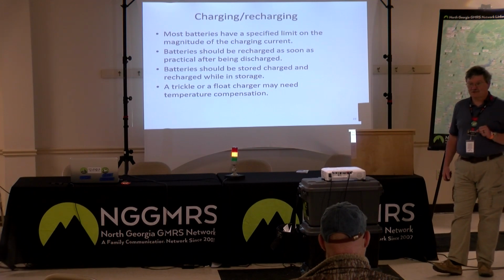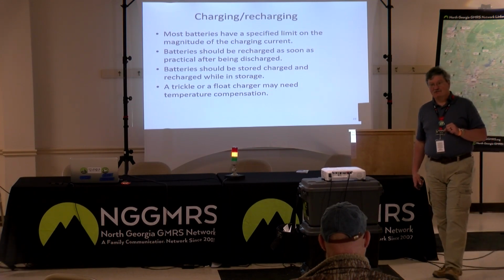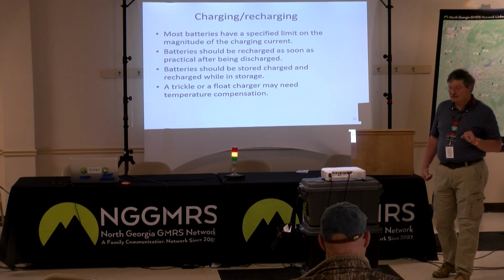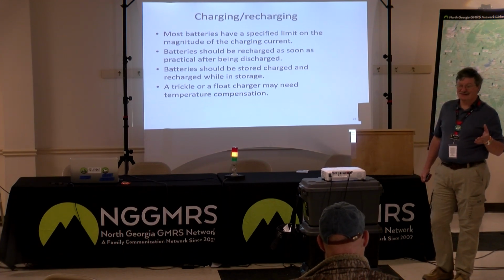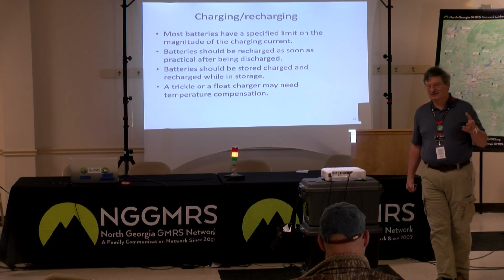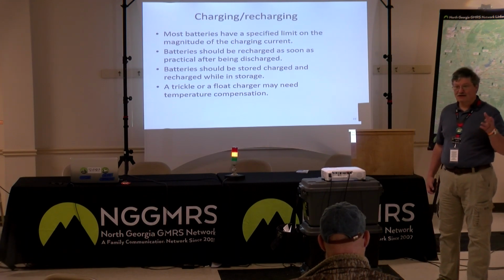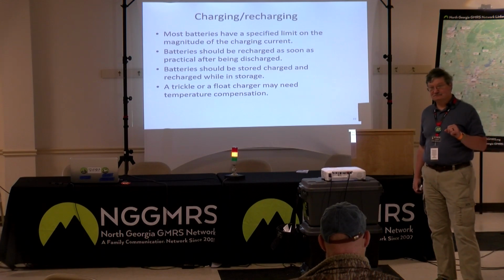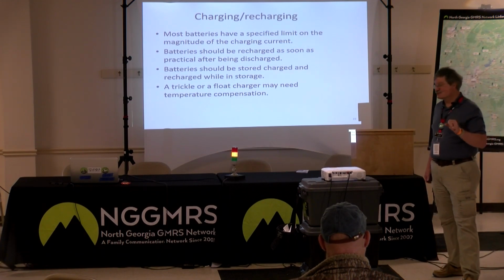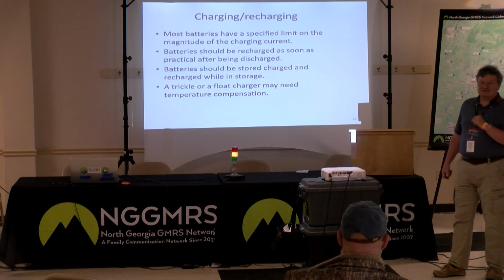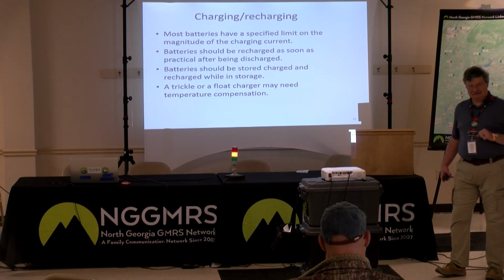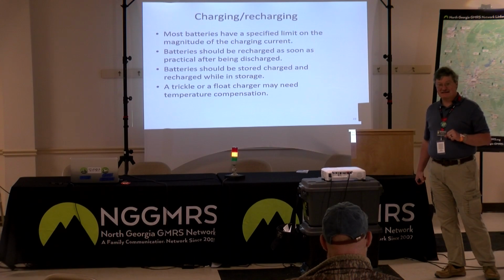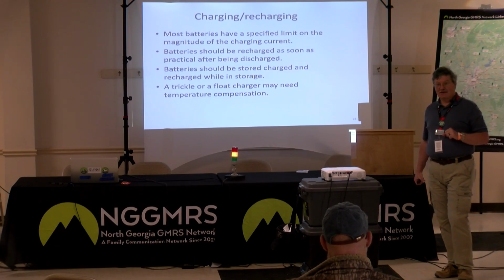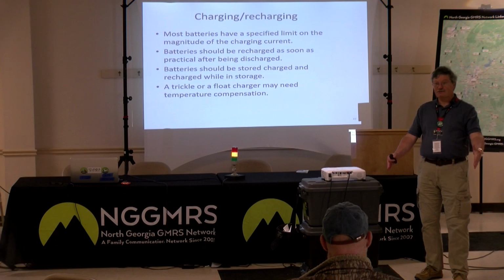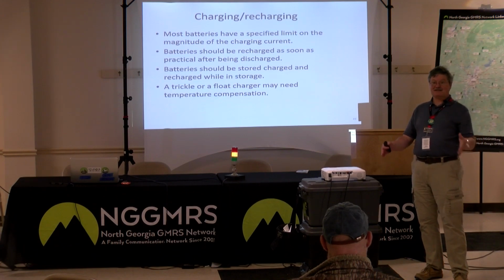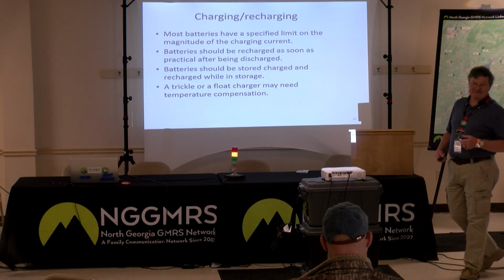So it'll do okay. And some batteries, especially some of the sealed lead acid product, there's no such thing as a sealed lead acid battery. I don't care what they tell you, they're valve regulated. And I can go into a lot of story on that. But what happens is some of the batteries may self-regulate how fast they can charge, to where I put this voltage on it and that's all it will accept. It self-regulates. Other batteries may have to have external regulation.